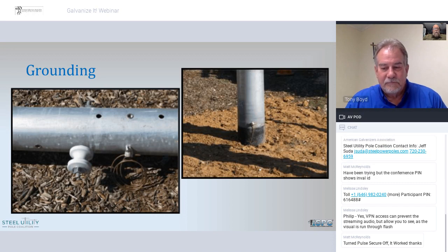Linemen are pretty familiar with the fact that when you're untying and taking control of the thin tie wires that tie the conductor to the insulator, they control it so that it won't hit anything as they're unwrapping that long piece of copper wire or that long piece of aluminum wire. But they also know that if they accidentally do strike a cross arm, it's just going to smoke a little bit. It might pop a little bit. And when they get out the steel arms and steel poles, they treat that differently. And that's a mistake. All poles, arms, everything should be treated exactly the same. Cover up, everything should be considered as a difference in potential and covered and isolated in order to keep from contact. Go ahead, Tony. Thank you, Jim.